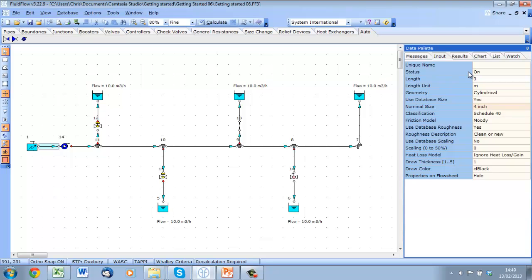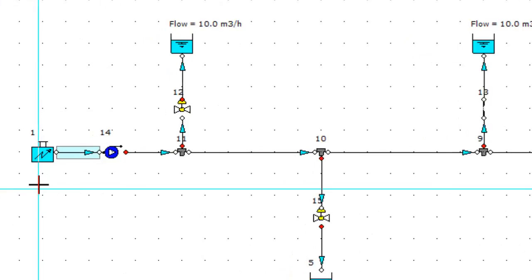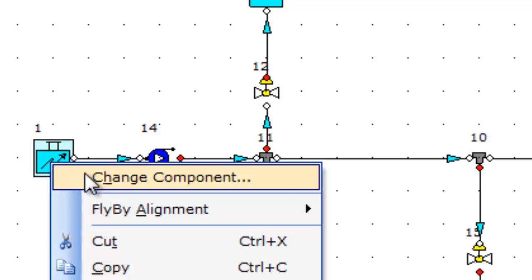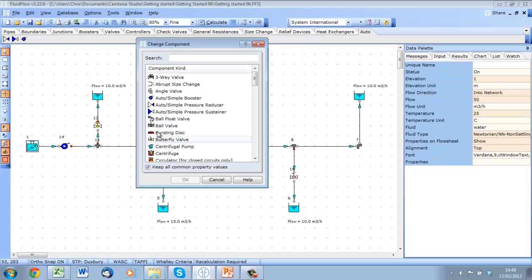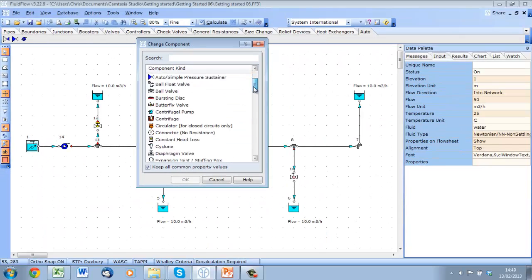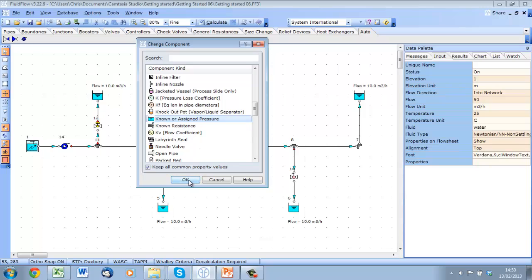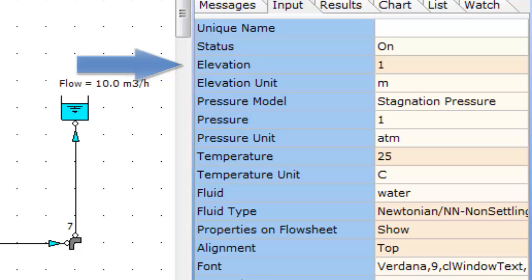Now that we have defined our duty flow at the auto booster, we can no longer do it at our inlet boundary. That's okay, because now this node represents the tank or reservoir on the suction side of the pump. So we can change it to a pressure node and assume that the tank is open to atmosphere. We can also give the tank a small elevation advantage to provide positive suction head to the pump.